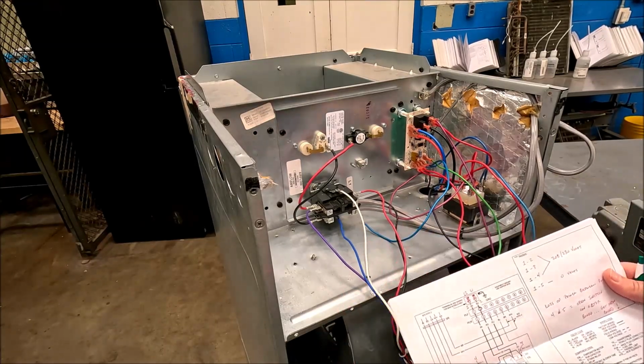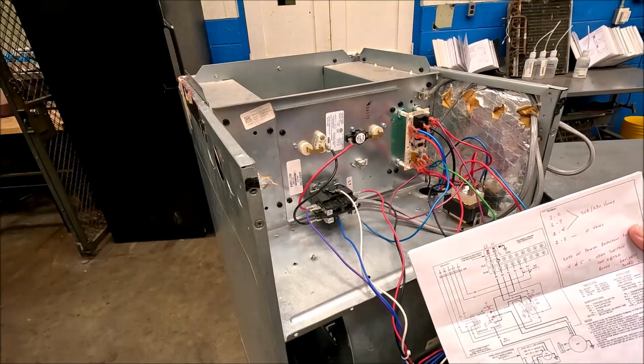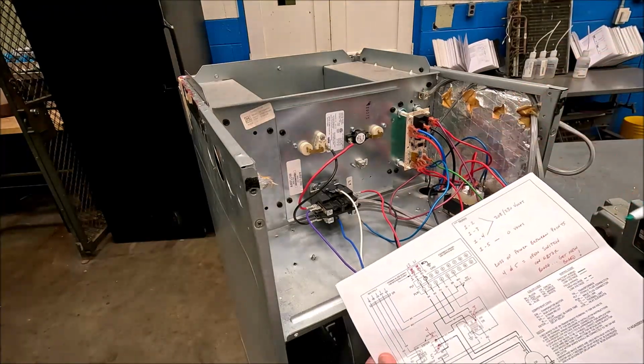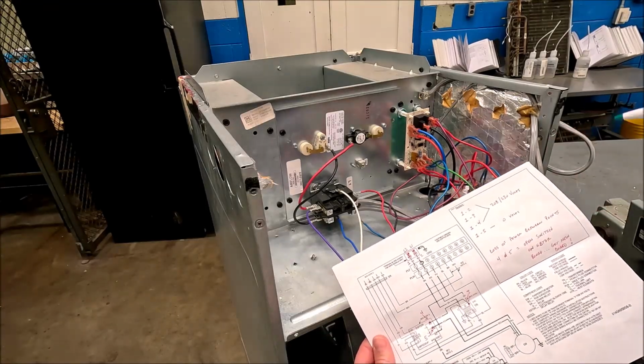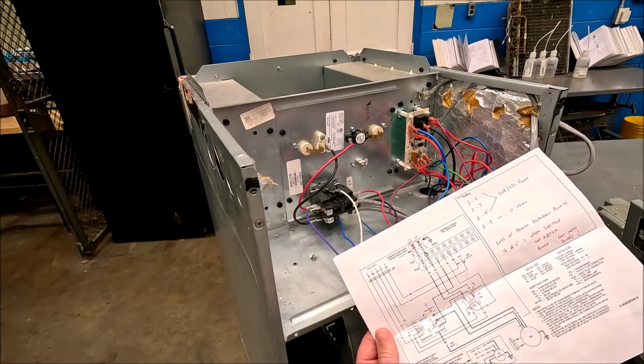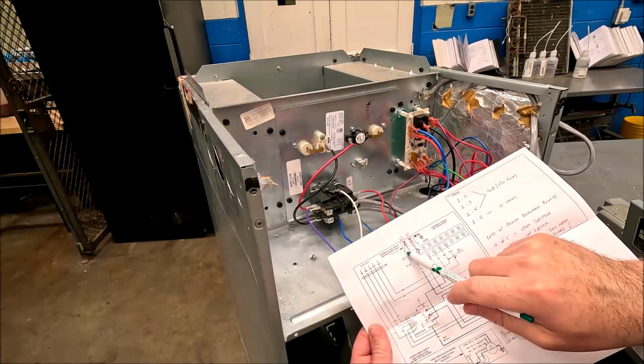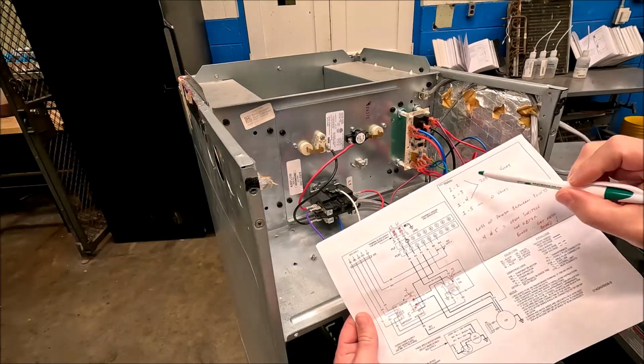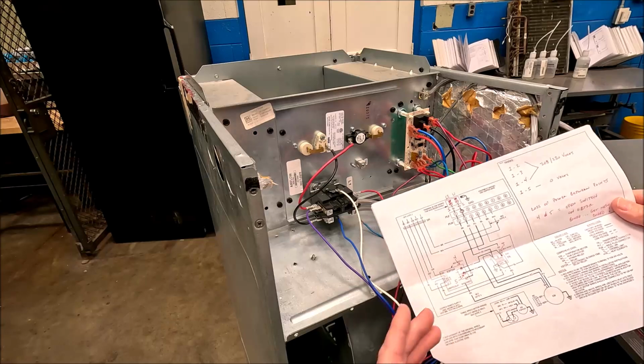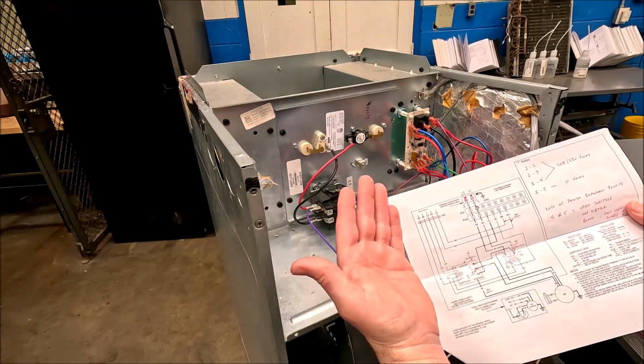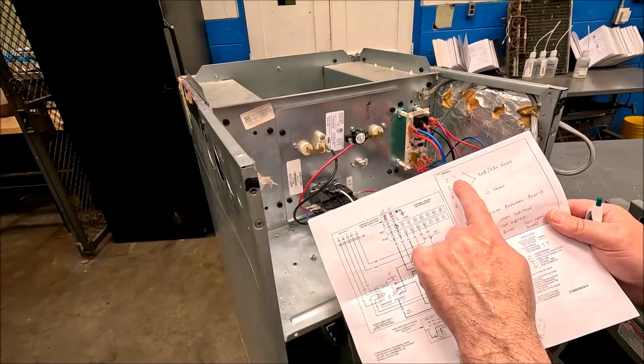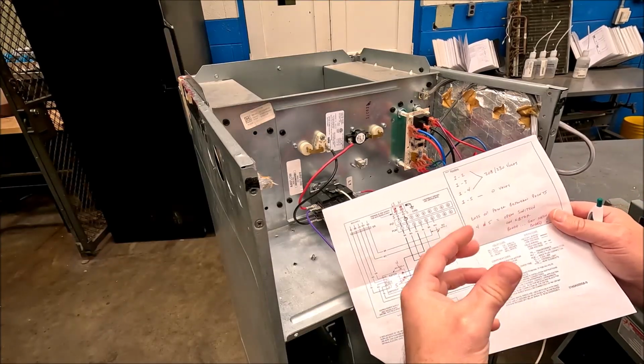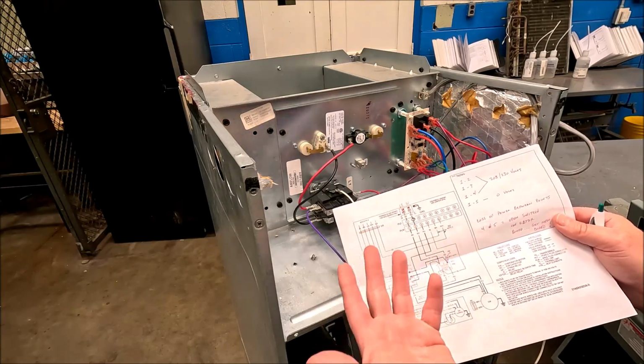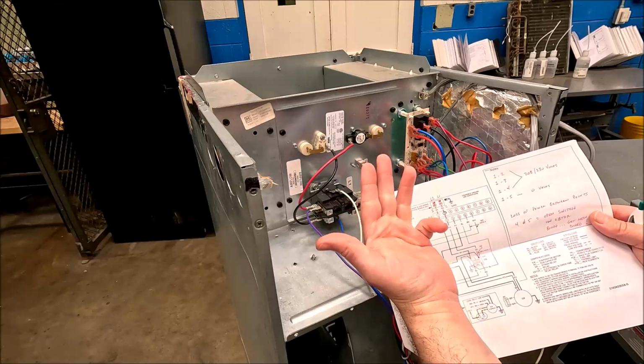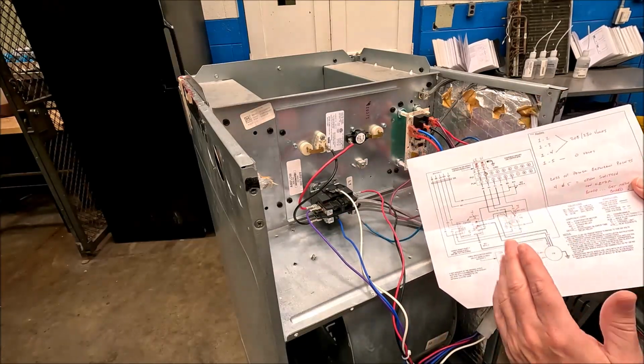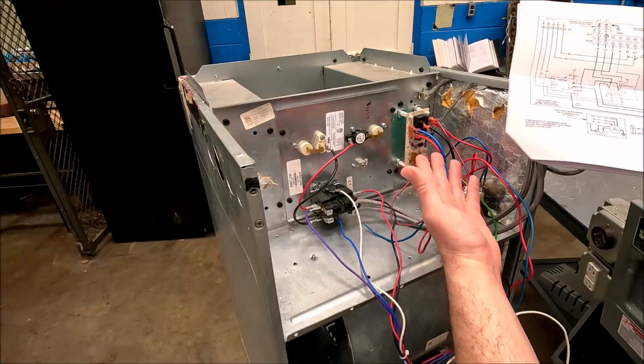So I'm gonna make a half a dozen little annotations, points to check in a circuit, and for this blower motor circuit, I've got 5 points that I've referenced down here. Number one is one side of power. That's my L1 side of power, or my L2 side of power, I should say. Everything else is gonna be an L1 check. So as I go down, and this is where the hopscotch plays in, I am writing out my hopscotch circuit, or my hopscotch checks to check in that circuit. And if I do just 3 or 4, power, control, load, return, right? Depending on how many different plugs you have or relays you have.